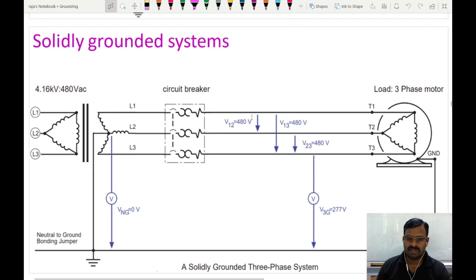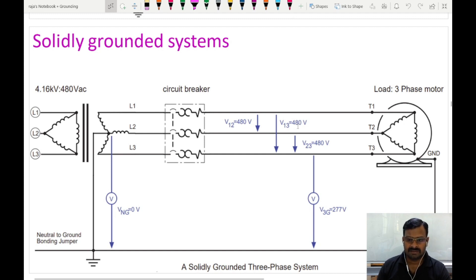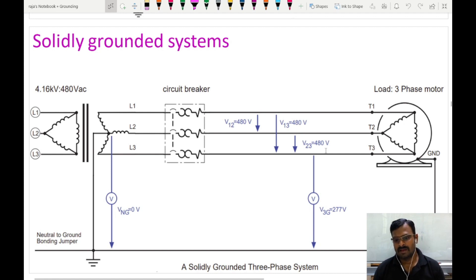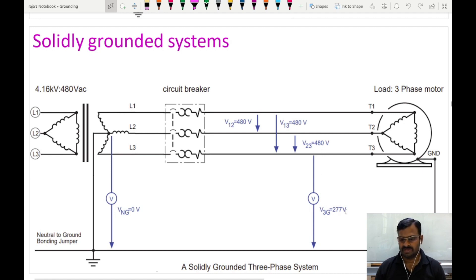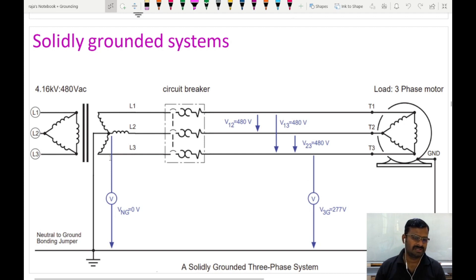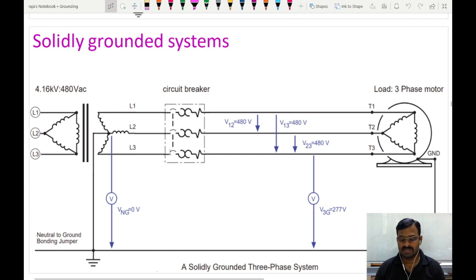As shown here, the line voltage is 480 volts: line 1 to line 2 is 480V, line 1 to line 3 is also 480V, and line 2 to line 3 is also 480V. The phase voltage is 277 volts. During a normal operating condition, the voltage or potential between the neutral point and the ground is 0 volts.